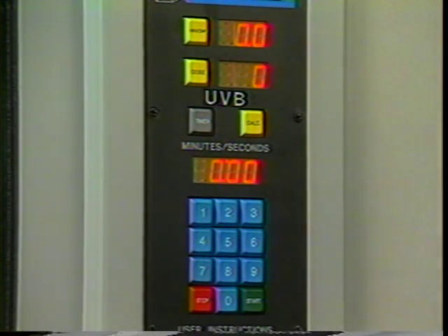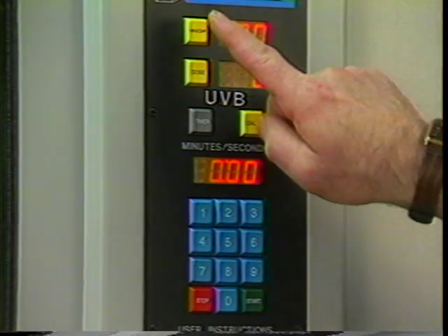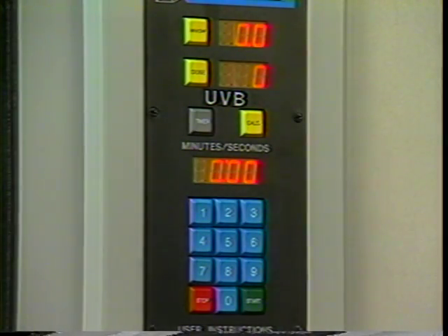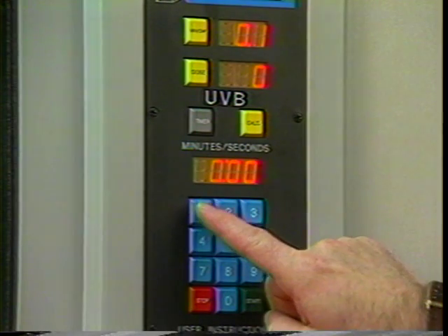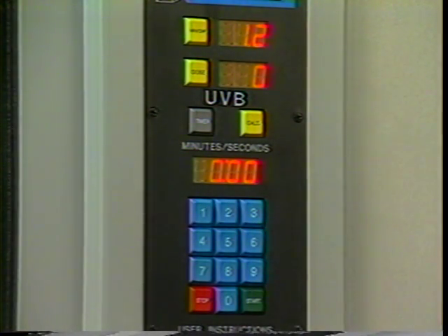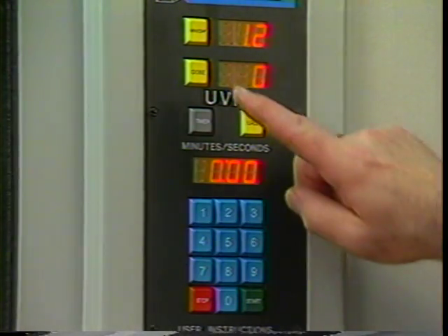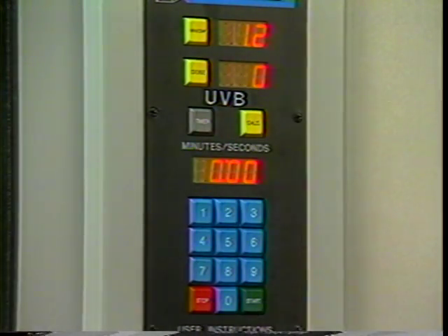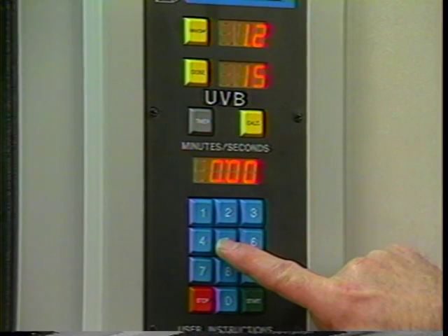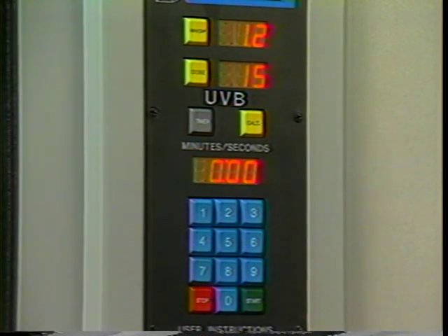Depress the topmost yellow button marked MW/cm squared on the PhotoSense timer and enter the reading from the appropriate meter. Directly below the first yellow button on the timer is another yellow button marked dose. Depress the button marked dose and using the keypad enter the prescribed dosage. Now depress the button marked calculate and the exact treatment time in minutes and seconds will appear in the display window.